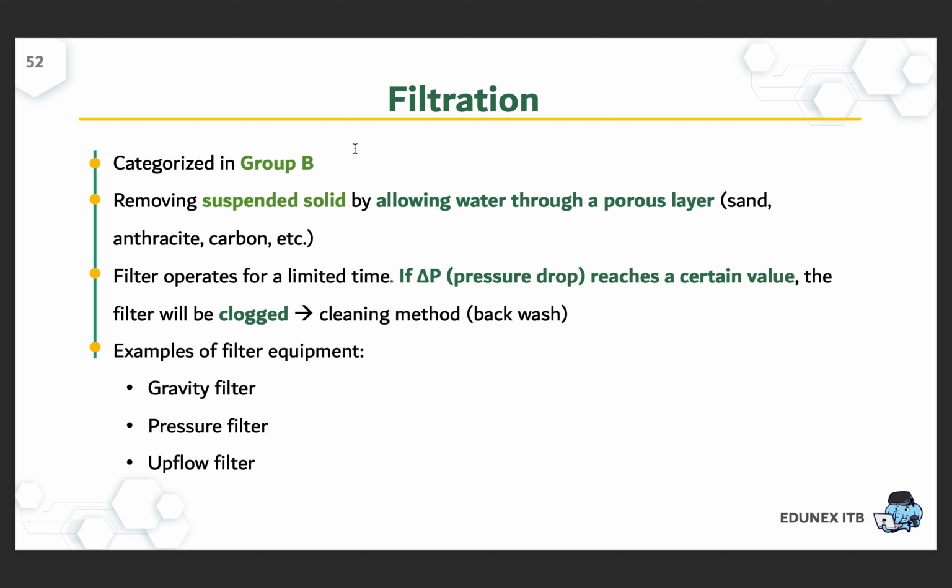Okay, so all filters operate for a limited time. One way to determine whether the filter's operation time should be ended or not is by observing the pressure drop. The pressure drop is the difference between inlet pressure and outlet pressure. So once the pressure drop becomes too high, that will be one clue that the filter has been clogged. And then once the filter has been clogged, we need to clean the filter. To clean the filter, we can use backwash.